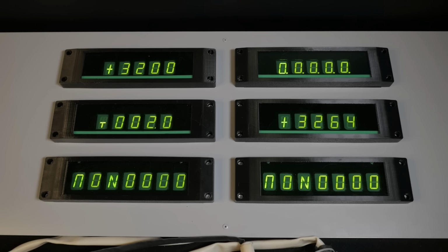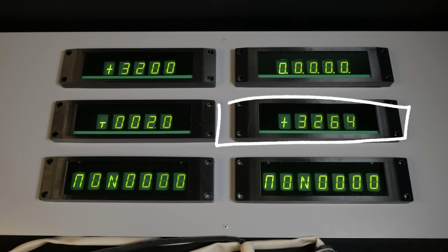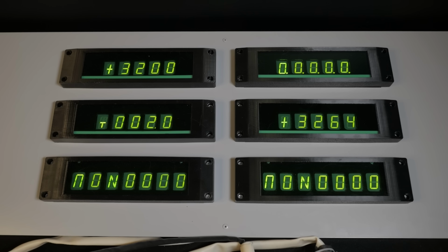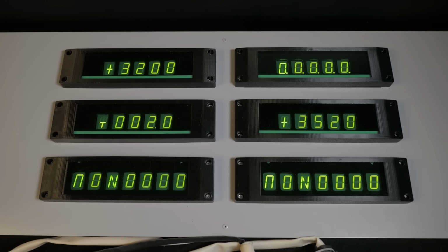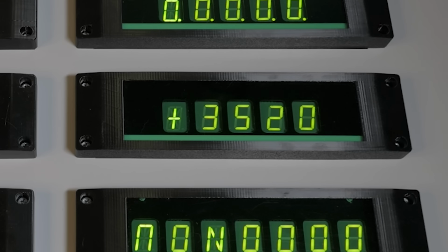The result is 3264 megawatts. That's exactly 2% above the nominal power. When this value is reached, an alarm will activate. But I also programmed a more extreme value representing a condition that is already no longer permitted. I select AP, which is emergency high set point, and the result is 3520 megawatts. At this power level in the real reactor unit there won't be any warnings, the emergency protection by reactor power will activate.